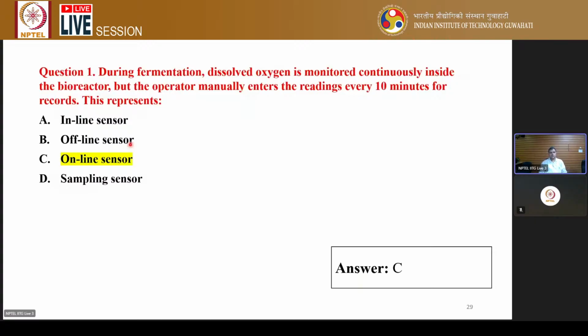It says in the case of inline, the monitored data is directly transferred to the controller. In the case of online, it is monitored but manually entered into the controller. And in offline, the data is also not monitored online - you have to take out the sample, analyze it, then you can enter it to the controller.